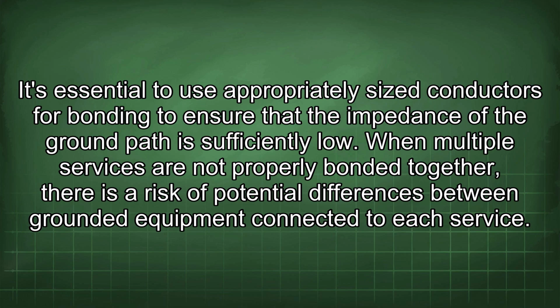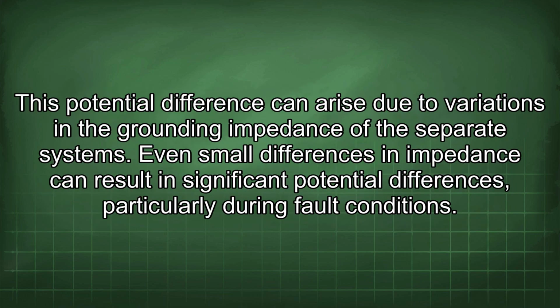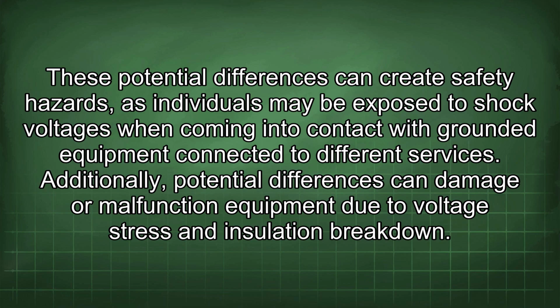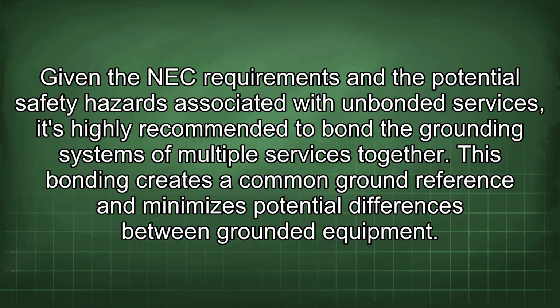It's essential to use appropriately sized conductors for bonding to ensure that the impedance of the ground path is sufficiently low. When multiple services are not properly bonded together, there is a risk of potential differences between grounded equipment connected to each service. This potential difference can arise due to variations in the grounding impedance of the separate systems. Even small differences in impedance can result in significant potential differences, particularly during fault conditions. These potential differences can create safety hazards, as individuals may be exposed to shock voltages when coming into contact with grounded equipment connected to different services. Additionally, potential differences can damage or malfunction equipment due to voltage stress and insulation breakdown. Given the NEC requirements and the potential safety hazards associated with unbonded services, it's highly recommended to bond the grounding systems of multiple services together.